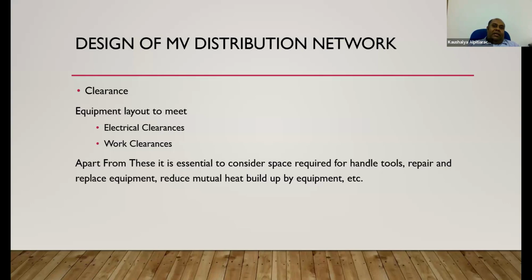If not, you are damaging all other equipment which is situated or placed inside the particular switchgear room, and building up mutual heat. So that may increase the working ambient, and can cause damages.